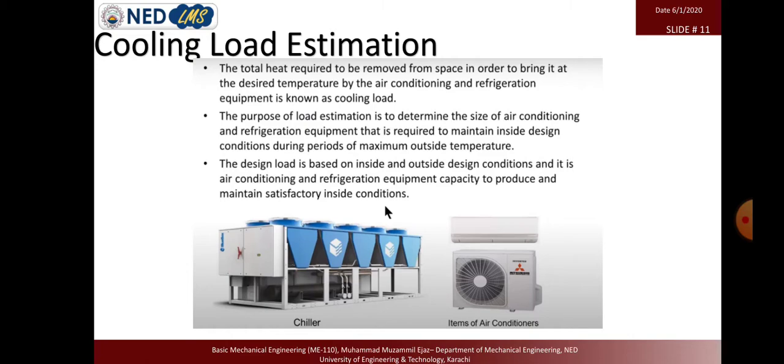The total heat required to be removed from a space in order to bring it to the desired temperature by air conditioning and refrigeration equipment is known as cooling load. The purpose of load estimation is to determine the size of the air conditioning and refrigeration equipment required to maintain inside design conditions during the periods of maximum outside temperature. The design load is based on inside and outside design conditions, and it is the air conditioning and refrigeration equipment capacity to maintain satisfactory inside conditions.